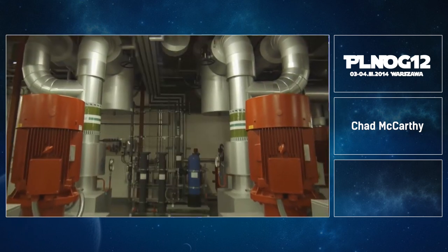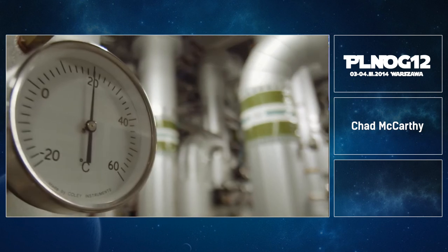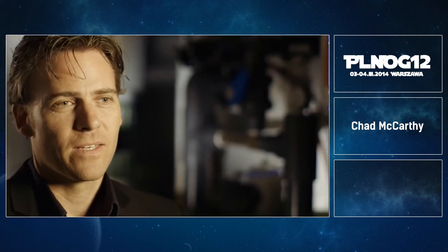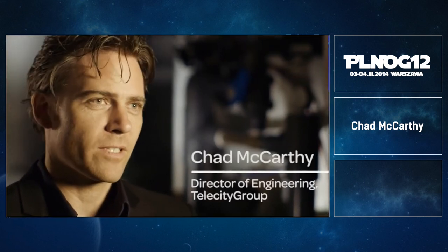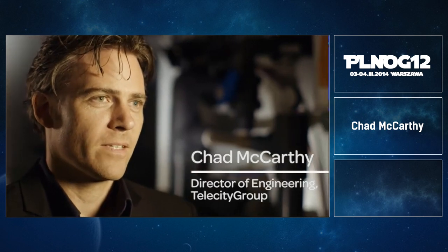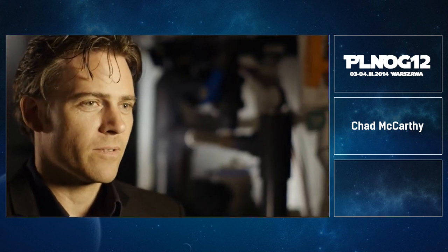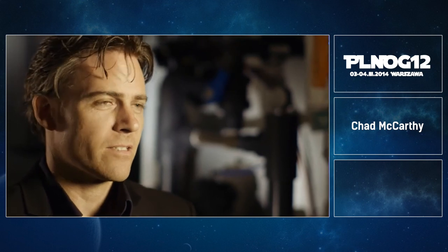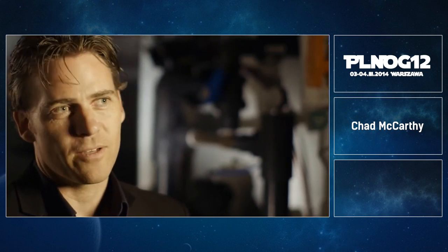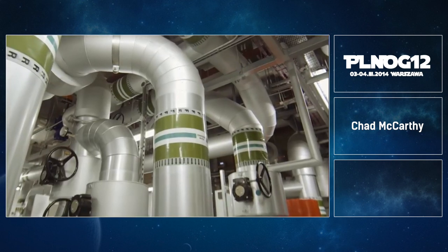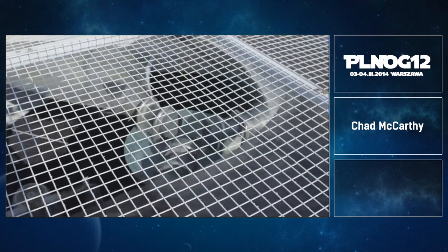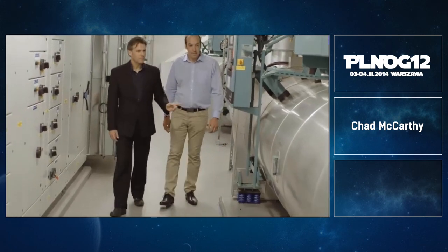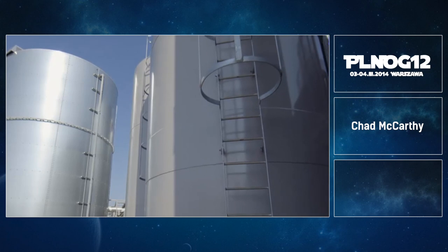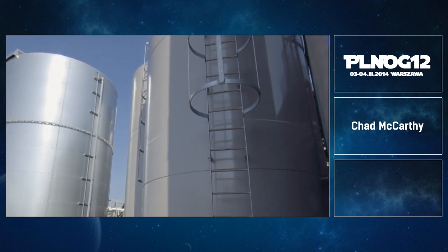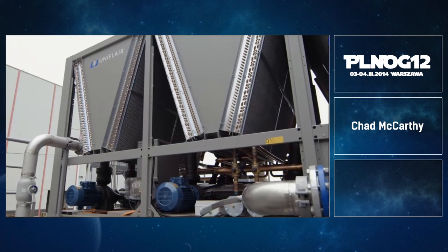Well, all energy used by IT equipment in the data halls themselves is converted to heat. And if left unchecked, this heat will accumulate and cause an overtemperature in the data center. So the two highest risks of failure in a data center are either electrical supply failure or overtemperature. So it's extremely important to have a good, reliable cooling system. The environmental strategy of a data center is extremely dependent on the cooling solution.